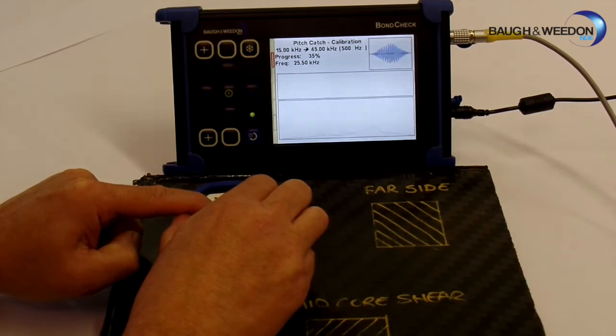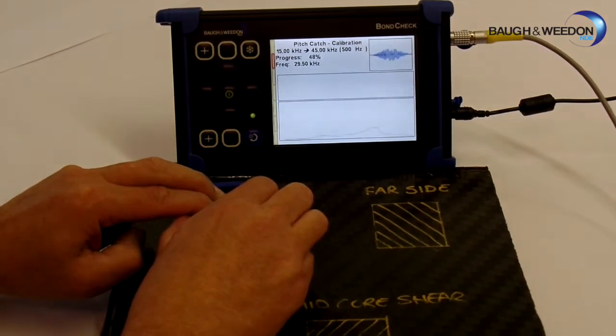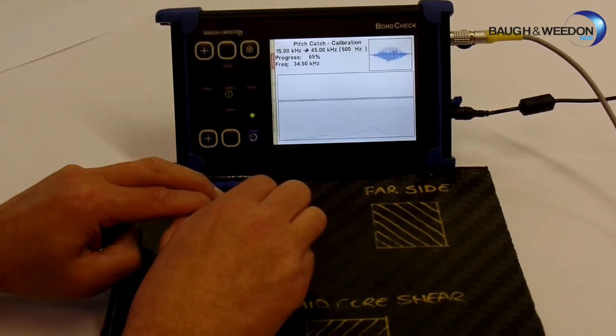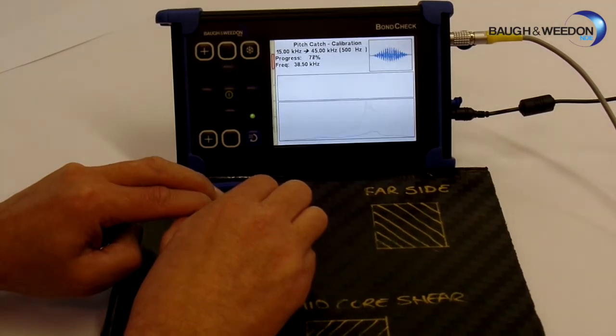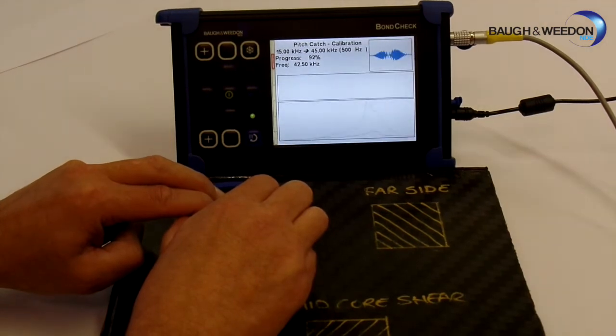And now there is a green line, not that you can probably see it on the screen at the moment, but there is a green line being written on the bottom where the amplitude is, and the difference between them is because of the disbond. Nearly finished.